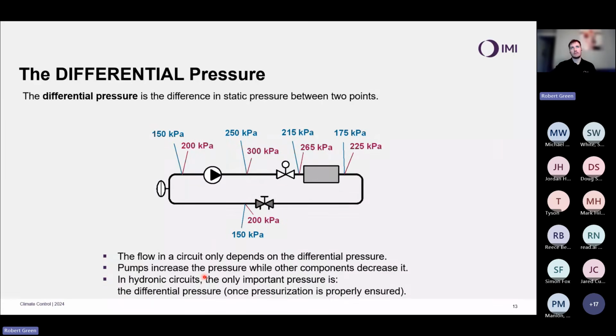Because if we look at this system here, if we said at design conditions to have the design flow through this system, we have a pump. And let's say we started at 150 kilopascals. My pump adds 100 kilopascals. 150 to 250 is 100.